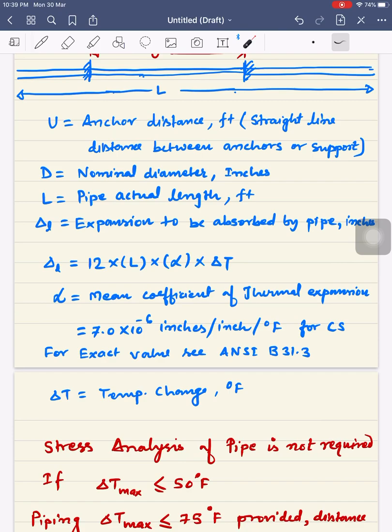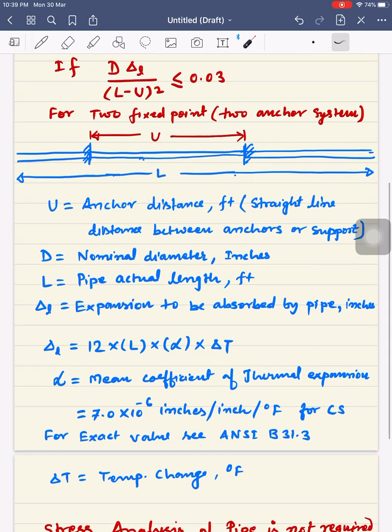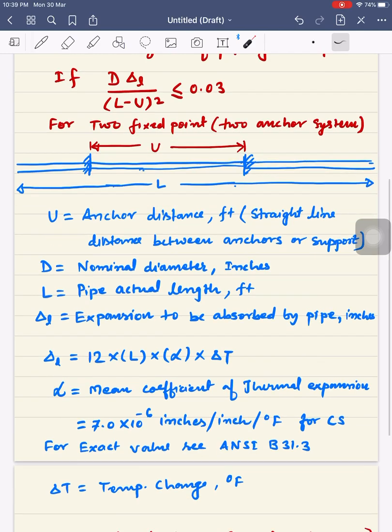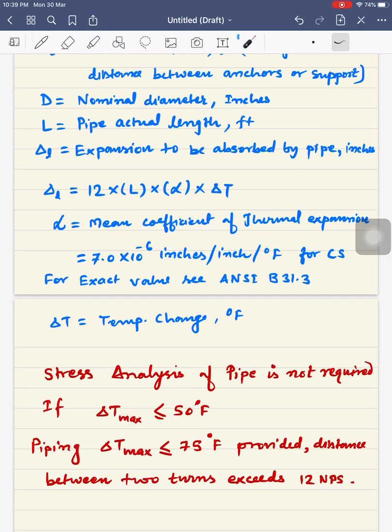When fluid is flowing through the pipe and the temperature variation is there, the pipe will have thermal expansion. Because of that, the pipe may expand. This alpha value is around 7 times 10 to the power minus 6 inches per inch per degree Fahrenheit for carbon steel.